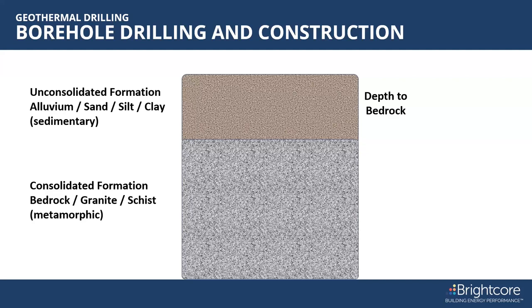The idea with thermal conductivity is that it can store or transfer heat energy, holding, moving, or as we say, diffusing it. Once the first hole is made to avoid sloughing, or the hole collapsing on itself, we case off with steel casing, usually schedule 40, typically down to the bedrock, and then continue drilling within the bedrock.